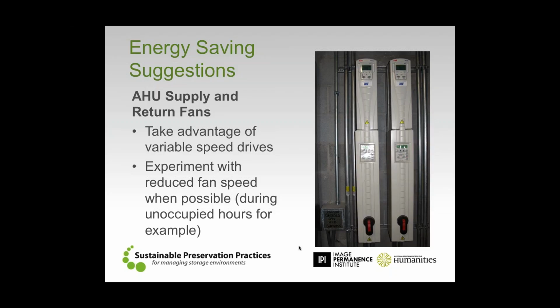There's no set fast amount that you can adjust the quantity of air that moves through, but between shutdown experimentation and setback experimentation, looking at fan speed, we've come to realize that oftentimes the amount of air that we send to the spaces has been over-designed or overestimated, or at least conservatively estimated, when we started looking at the initial design of a system in the building. So the possibility here is to start experimenting with reduced fan speed when possible, especially during unoccupied hours, or even at night, even if there's just less occupation in the building. If there's less occupation, oftentimes there's going to be less energy load.